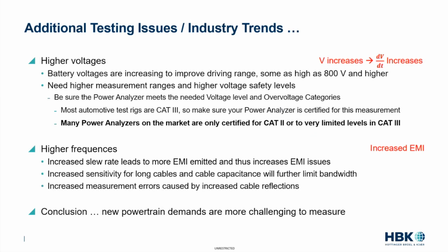And those include things like higher voltages. Battery voltages are increasing to improve driving range, and some of them are as high as 800 volts and some even higher. So that means you need to have higher measurement ranges. You also have to have higher voltage safety levels, and you want to be sure the power analyzer meets the needed voltage level and overvoltage categories. In fact, most automotive test rigs are Cat 3, so you want to make sure your power analyzer is certified for this measurement. Many power analyzers I've seen on the market are only certified for Cat 2 or very limited in levels in Cat 3.